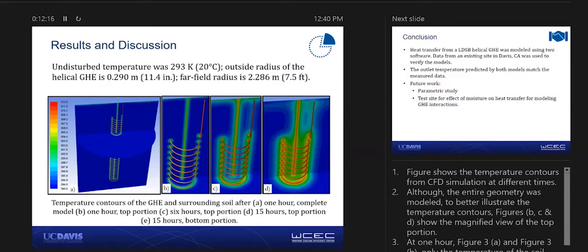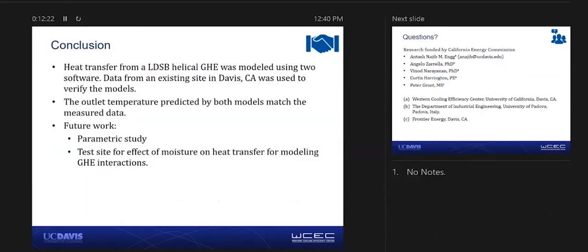So this way, we have calibrated and validated the capacitance resistance model. We can see that the heat transfer from a large diameter helical GHE was modeled using two software packages. The outlet temperature predicted by both models matched the measured data, and they matched each other.